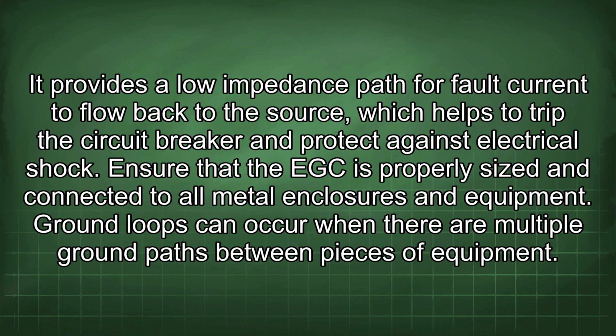It provides a low impedance path for fault current to flow back to the source, which helps to trip the circuit breaker and protect against electrical shock. Ensure that the EGC is properly sized and connected to all metal enclosures and equipment.